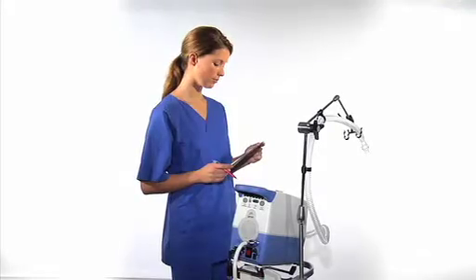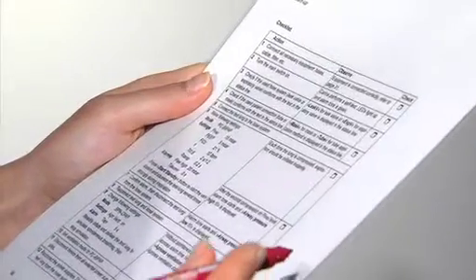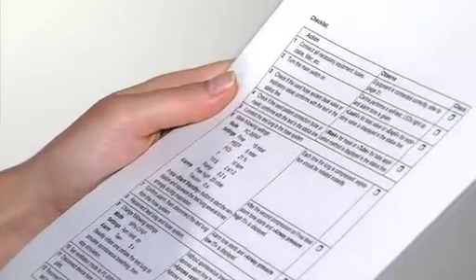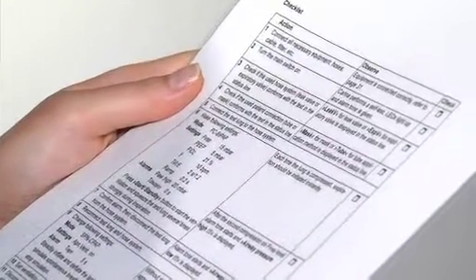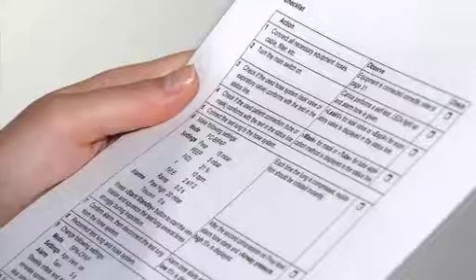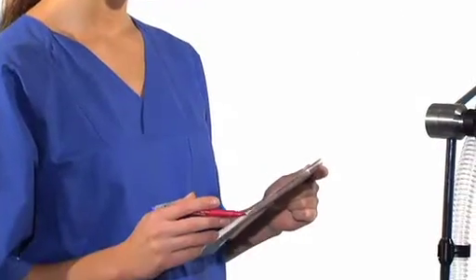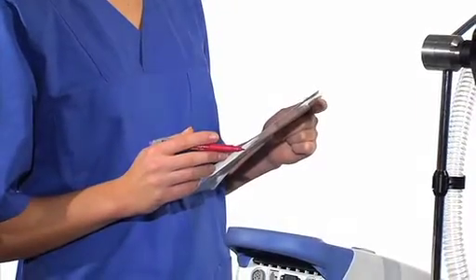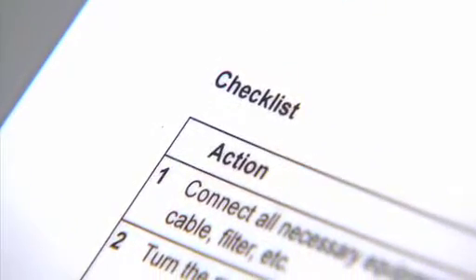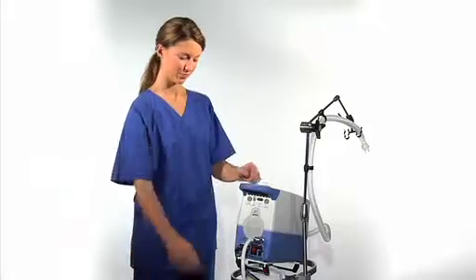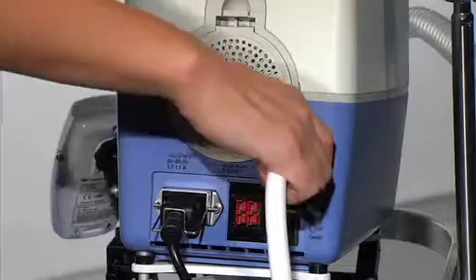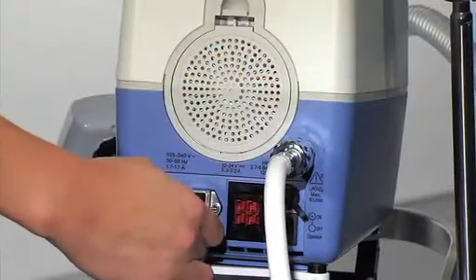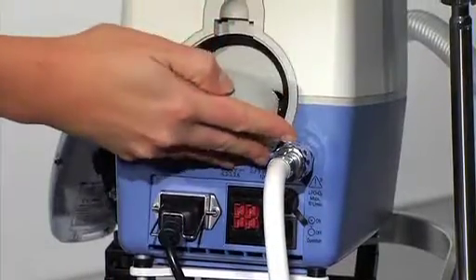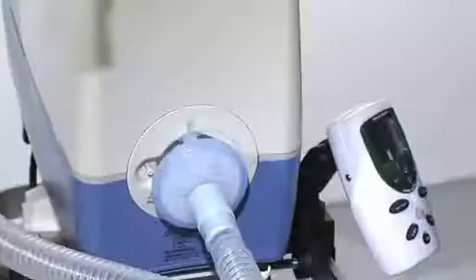Before connecting the patient, we recommend performing a system check to ensure the device is fully functional. The checklist for the system check is contained in the Carina instructions for use. The system check is fast and easy to perform and takes as little as 5 minutes. The check includes the following steps. Make sure that all the necessary equipment is connected correctly, including the high-pressure oxygen hose, power cable, HEPA filter, bacterial filter.